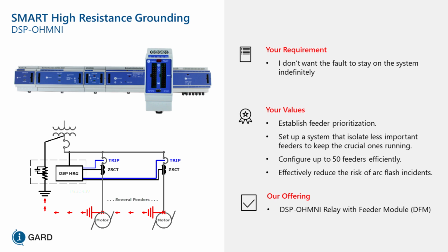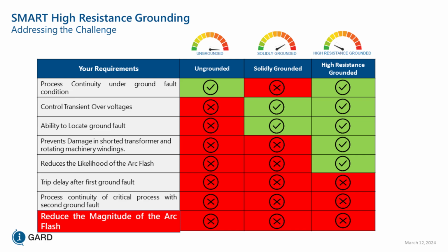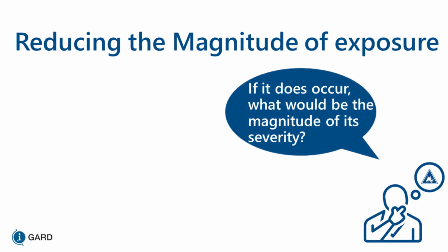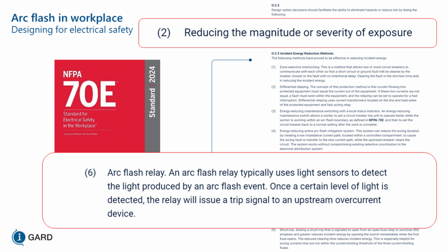The feeder with the lower priority will isolate, and will isolate quickly, before the instantaneous of your feeder breaker. Reduce the magnitude of the arc flash. Okay, now you're going to have to bear with me on this one. 70E says reducing the magnitude or severity of exposure. An arc flash relay will typically detect the arc flash and trip quickly.